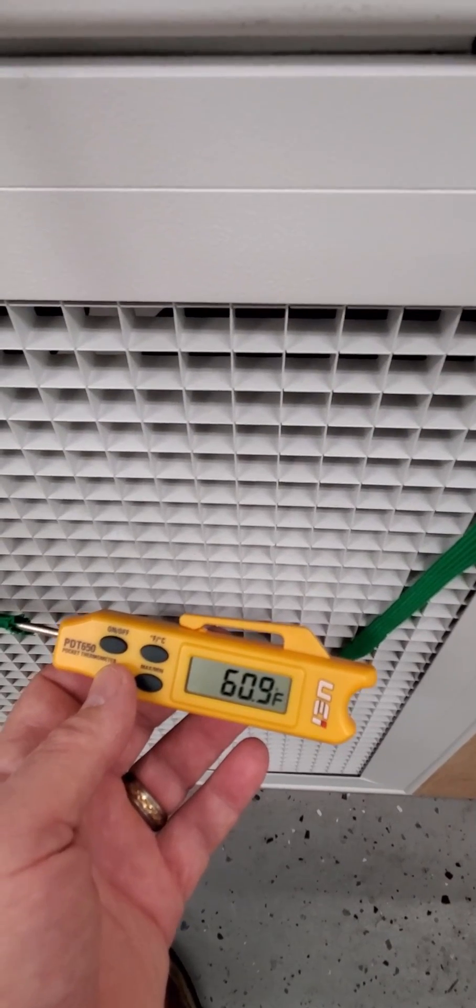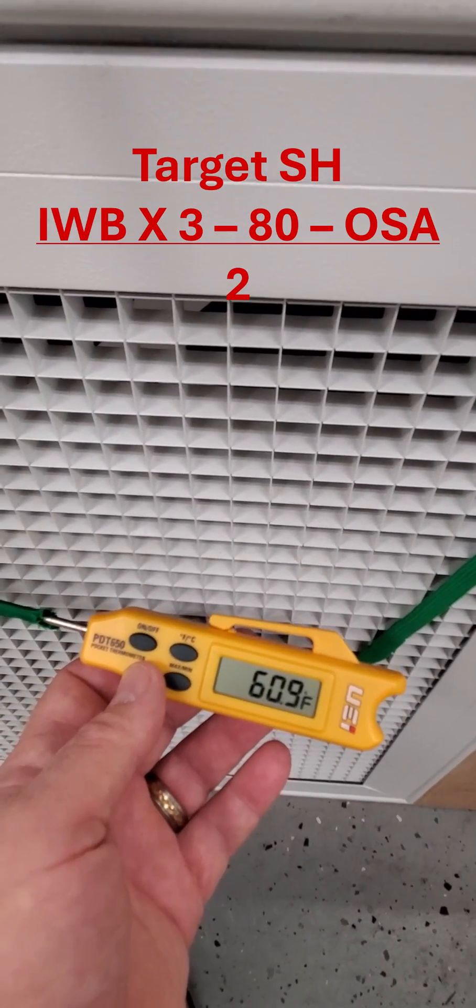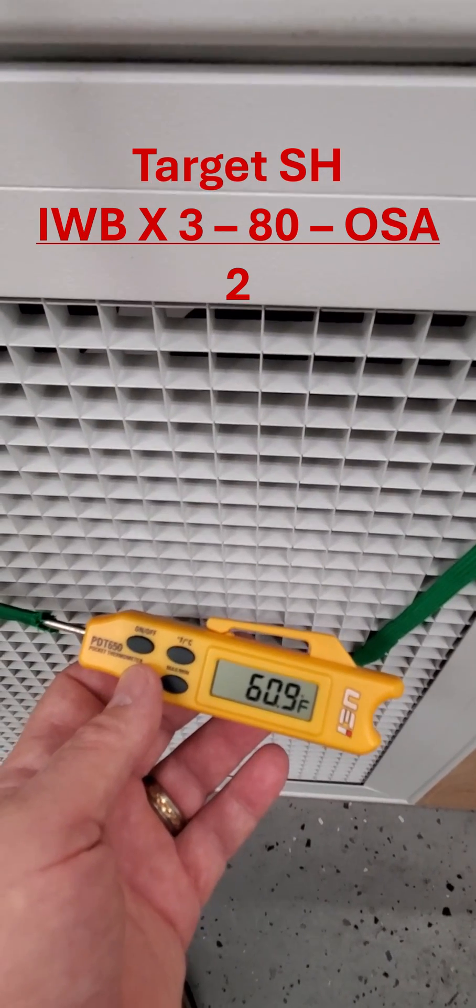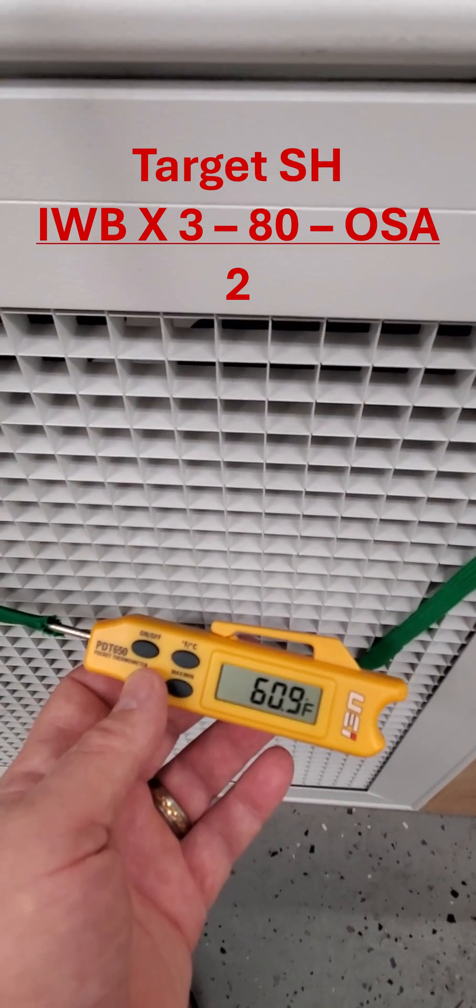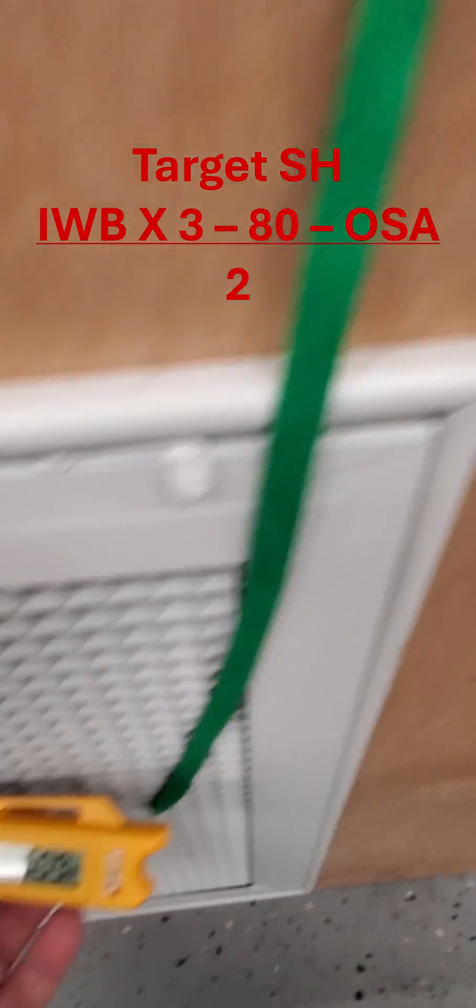What's the calculation for target superheat? Remember, it's the indoor wet bulb times three, minus 80, minus the outside air temperature. Divide all that by two, and you'll get your target superheat.